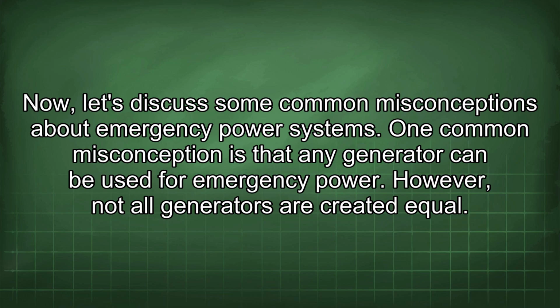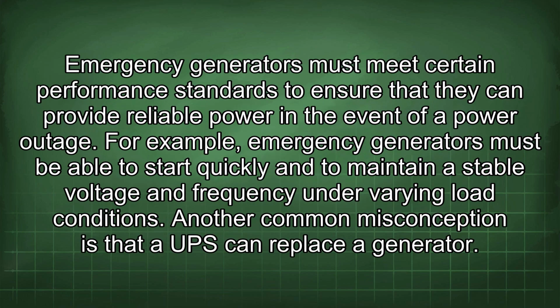One common misconception is that any generator can be used for emergency power. However, not all generators are created equal. Emergency generators must meet certain performance standards to ensure that they can provide reliable power in the event of a power outage. For example, emergency generators must be able to start quickly and to maintain a stable voltage and frequency under varying load conditions. Another common misconception is that a UPS can replace a generator.